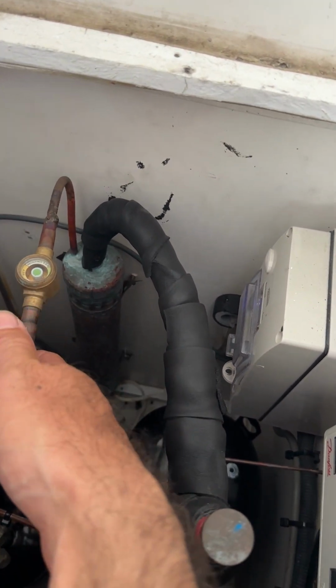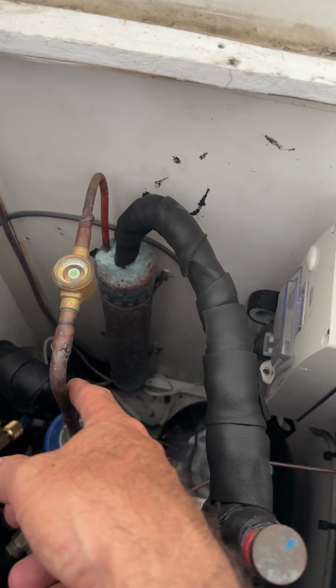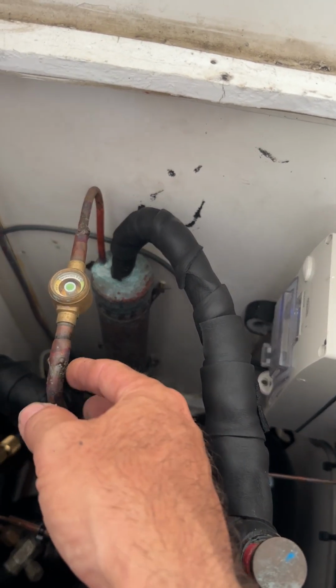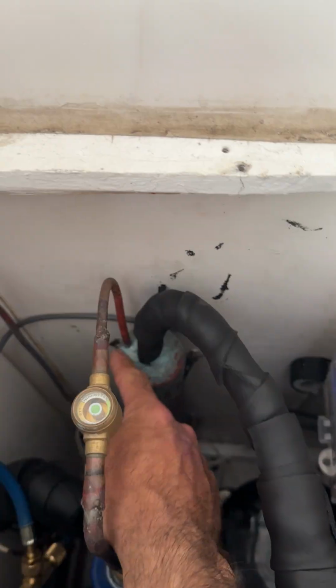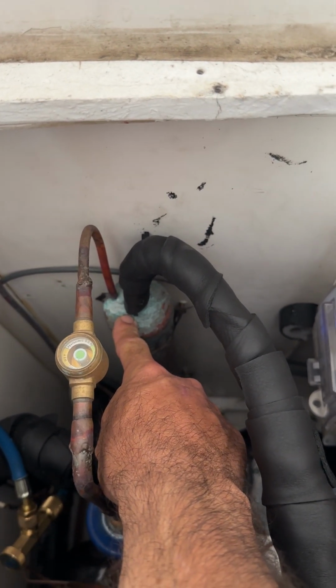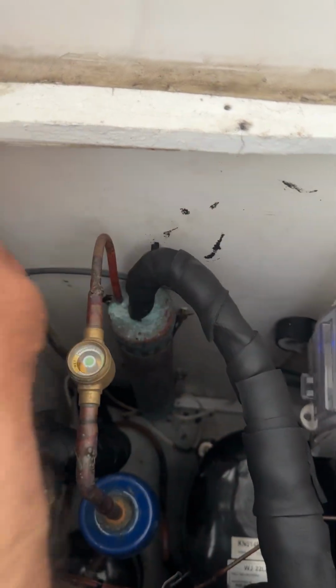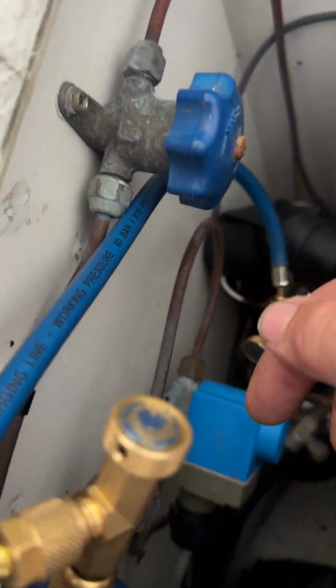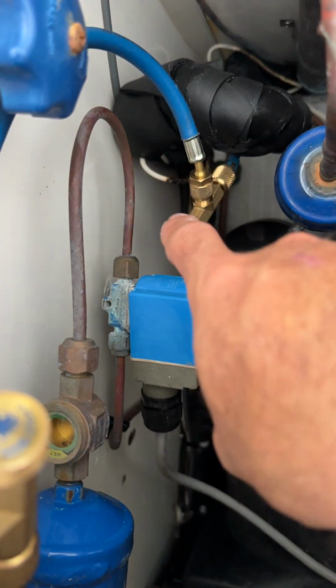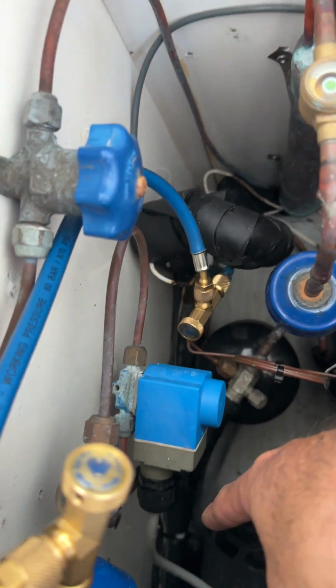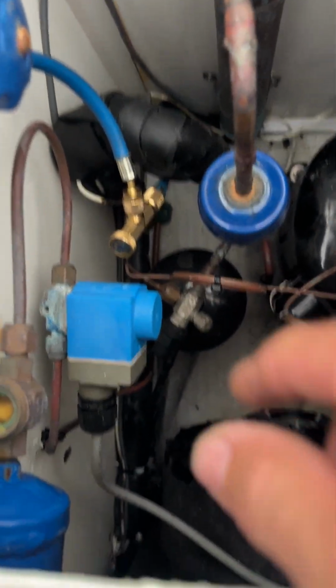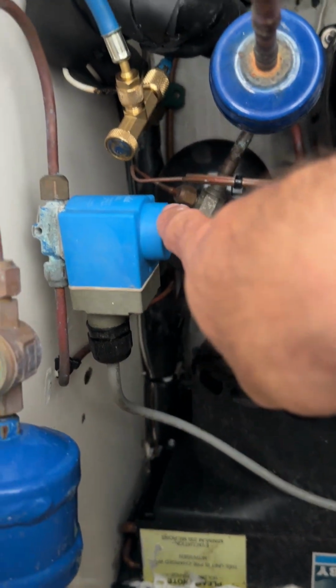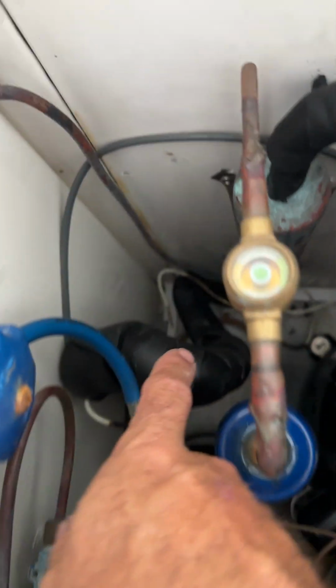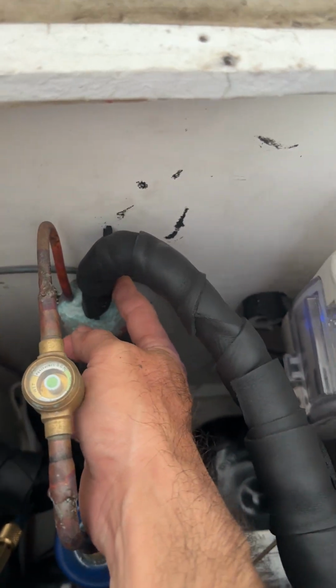So the liquid line, discharge liquid line from after the condenser is coming through here, and it goes downwards into this heat exchanger, and then it goes through and comes out, loops off the bottom there. Comes back through, and then it goes back around through to the solenoid valve, and it goes in through the TX valve, or your metering orifice. In this case, it's a TX valve. The suction basically comes up off the bottom there, and it loops around this loop, then it comes up through the bottom, and then it comes out from the top here.